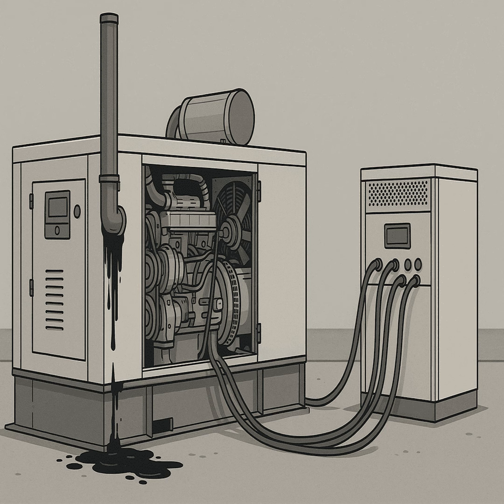The thinking is shifting. It might be acceptable to do an unloaded exercise run monthly, just starting it up to circulate fluids and check function, combined with a proper load bank test annually. Annually instead of monthly. Yeah. That could be a big saving in fuel and time. Huge savings, potentially less fuel consumption, less wear and tear from constant heavy testing, and some studies even suggest significantly lower overall emissions, maybe up to 70% less pollution compared to doing loaded tests every single month.